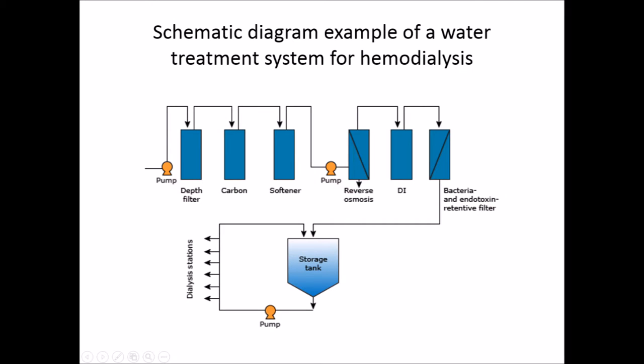This is a schematic diagram of a water treatment system for hemodialysis. Once the water has been purified by the RO system, the RO distribution system can either be a direct feed system or an indirect feed system. The direct feed system delivers product water from the RO unit directly to the loop for distribution. An indirect feed involves a storage tank in between, which accumulates product water delivered to the distribution loop, with the unused portion recirculated back into the storage tank.